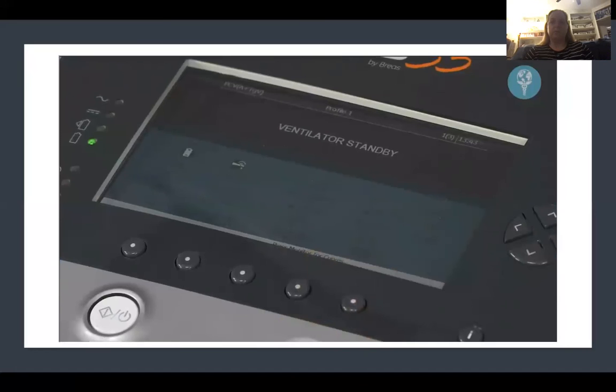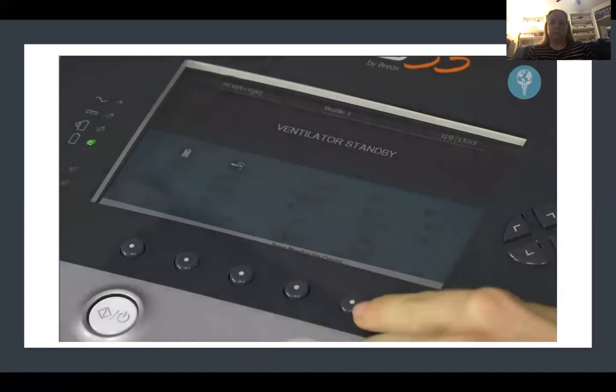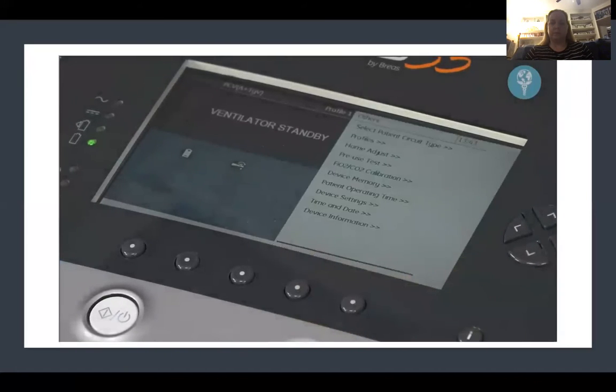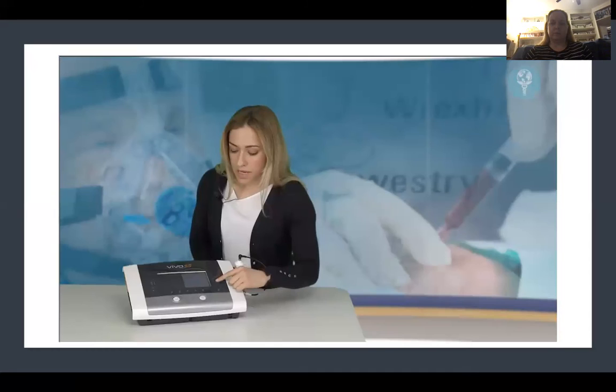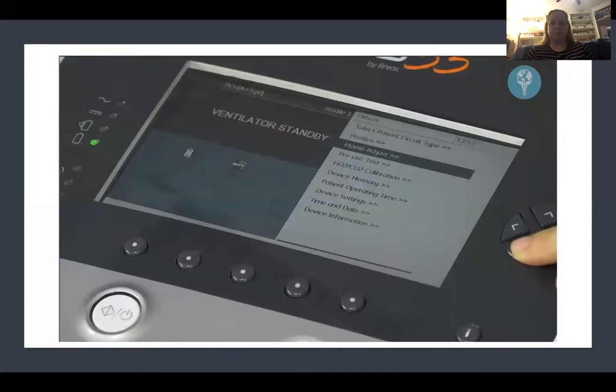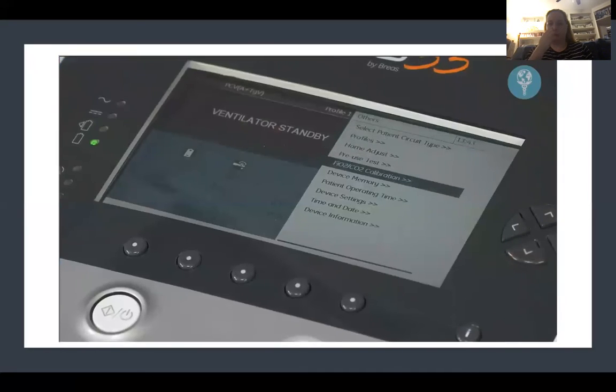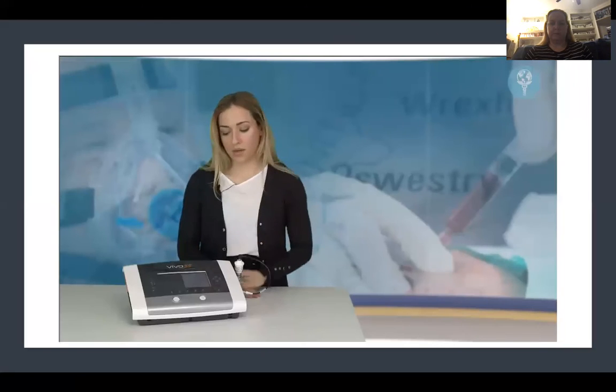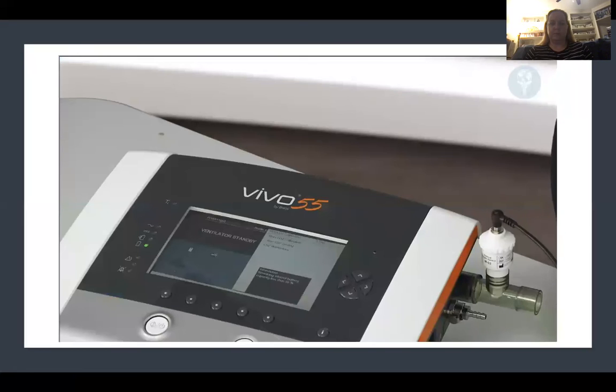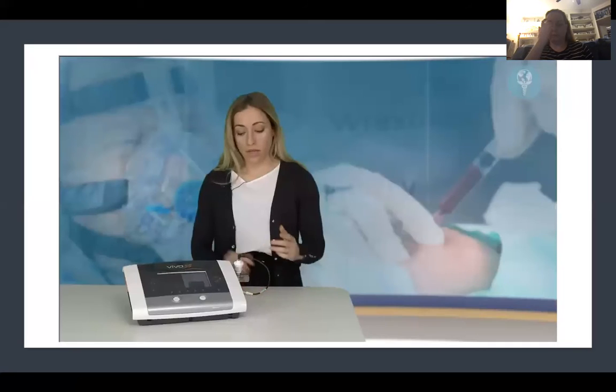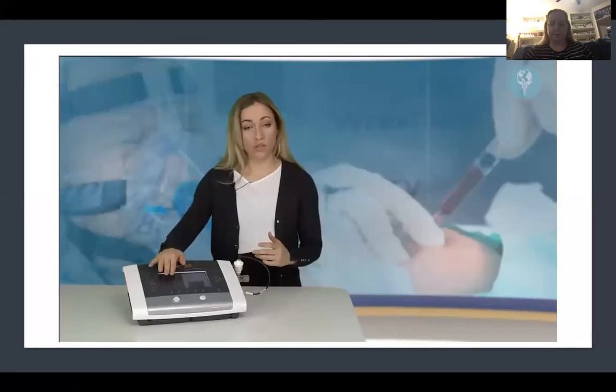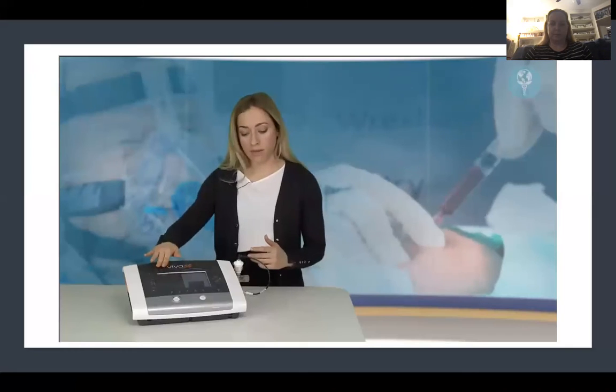And to access the calibration in the menu, we want the others menu. Push that button once. We can then scroll down with the down arrows until we get to FiO2/CO2 calibration. Then push the arrow to select that, and the device will take you through the step-by-step process of how to do that. Once the FiO2 sensor has been set up and is ready to use, it will tell you the fraction of inspired oxygen on the screen when the ventilator is running.